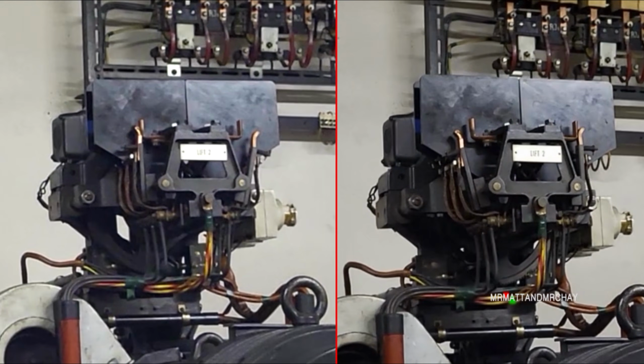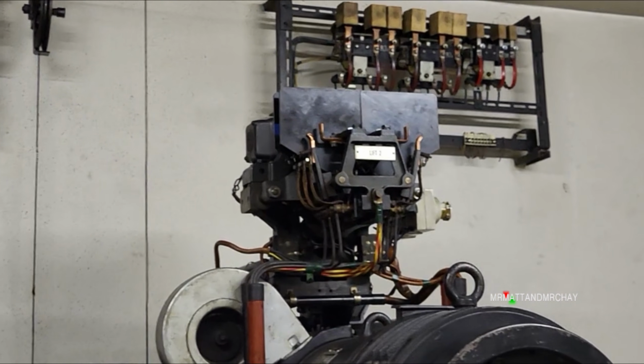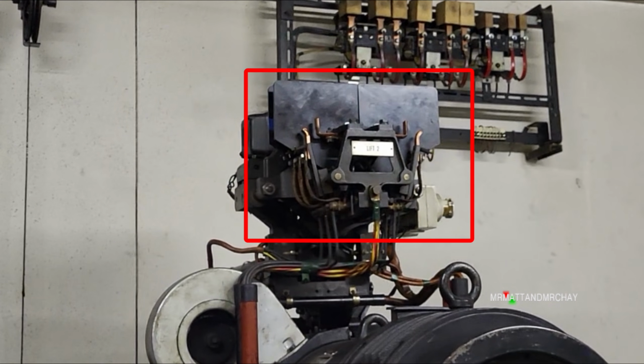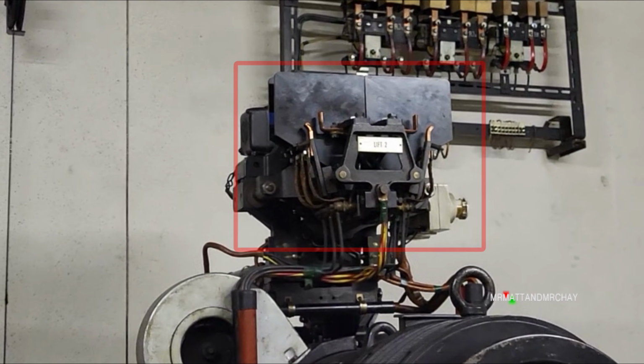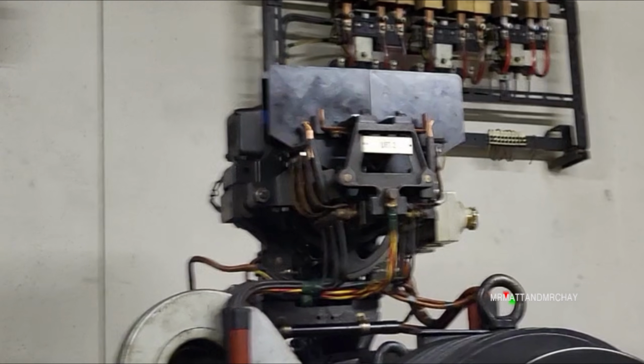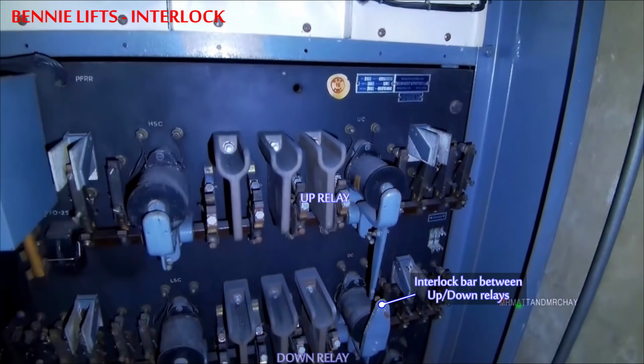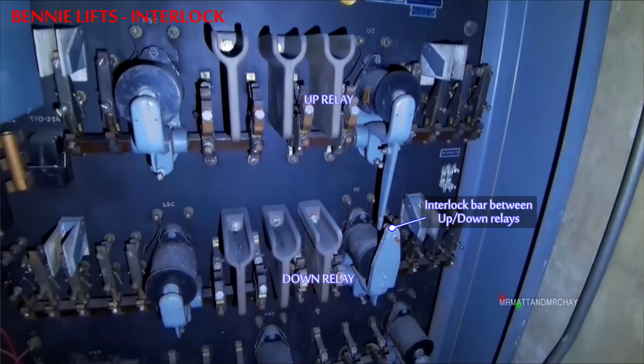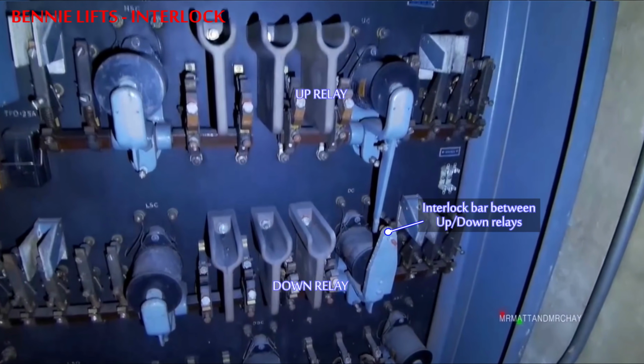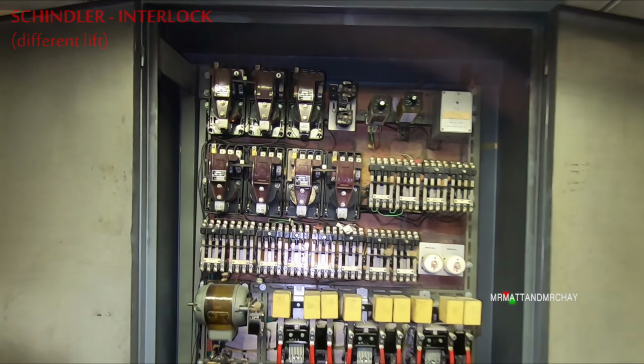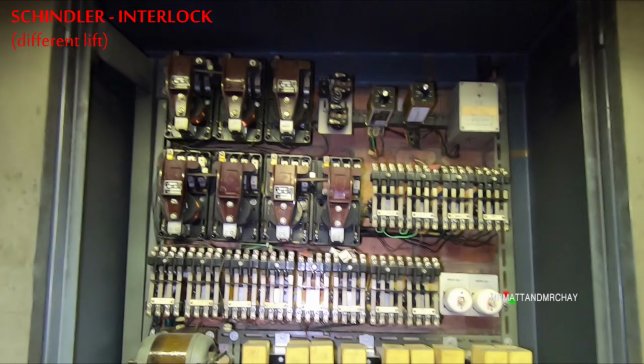From what I can see, there are a couple of reasons. And it's related to the contacts that you can see on either side here. The first reason is to form an interlock. It prevents the up and down motor control relays coming on at the same time. If this happened, 2 high voltage phases would short circuit.